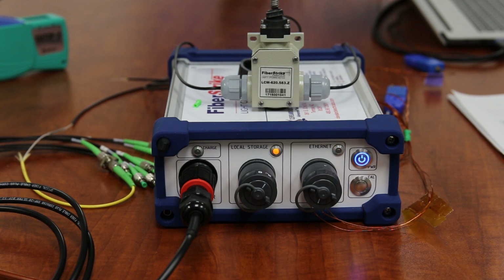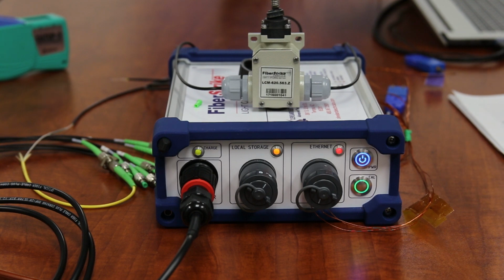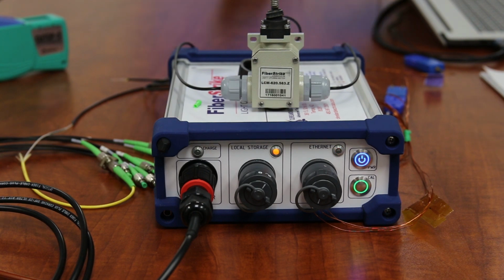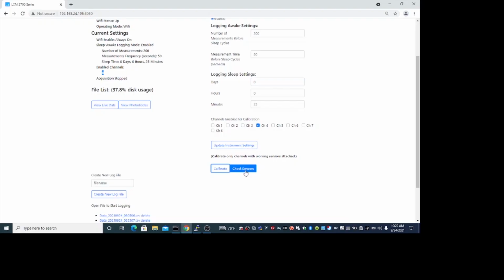Once it's done calibrating, the calibrate run button will have a solid green appearance. In addition, this header will disappear once the calibration is finished. Okay, the calibration just finished. Now we want to check our sensors.